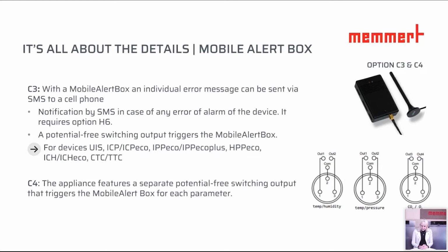And here we can see we have an out1 and an out2. Out1 is the switching contact for the SMS message whenever the maximum value of temperature is exceeded, or the minimum value of temperature is not reached, or the automatic ASF tolerance band is not correct and gives an alarm, or the mechanical temperature limiter is triggered, or even the temperature sensor is defective. Out2 is when the maximum value of humidity is exceeded, if the minimum value is not reached, or also if the humidity sensor is defective. We have this potential free switching output also for the vacuum oven.